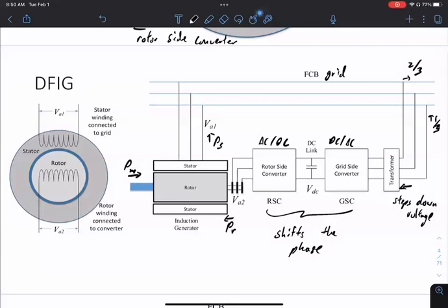Yeah, so you need the current to be fairly large. Active power also has to go out this side. It's hard to design a case where there's no active power going out this side. So you need active power to go through both, and you have about 2/3, 1/3. In a modern turbine, this is how the balance is. So these are big things.